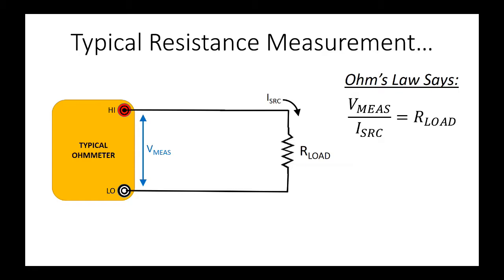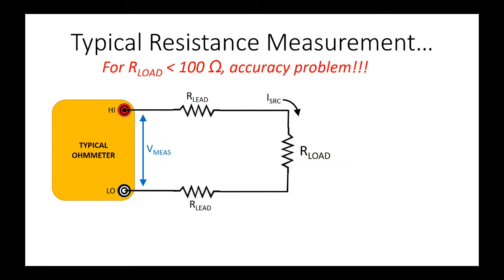The resistance value is calculated using the sourced current and measured voltage values. When your resistance values are greater than 100 ohms, this is probably fine. However, when you start measuring lower resistances, you will notice that your measurements hold some error.